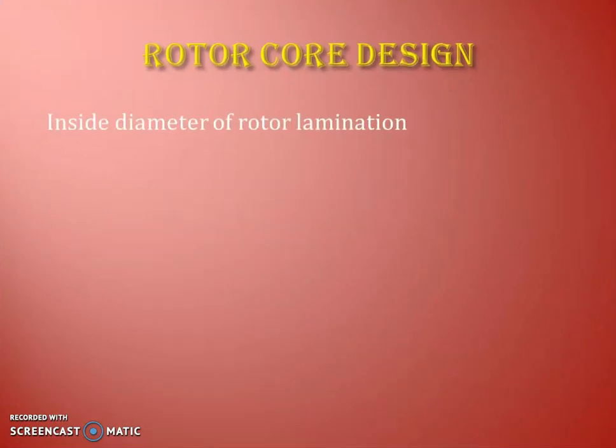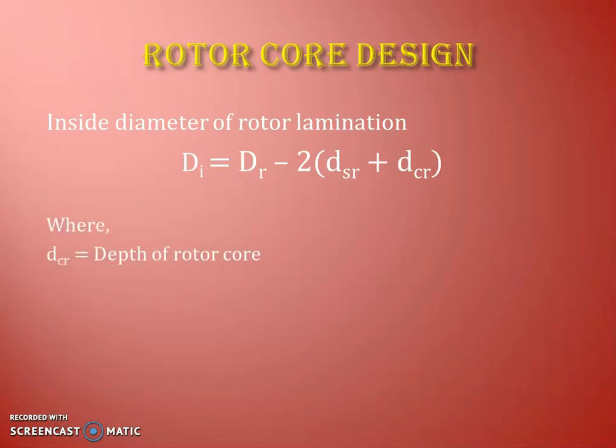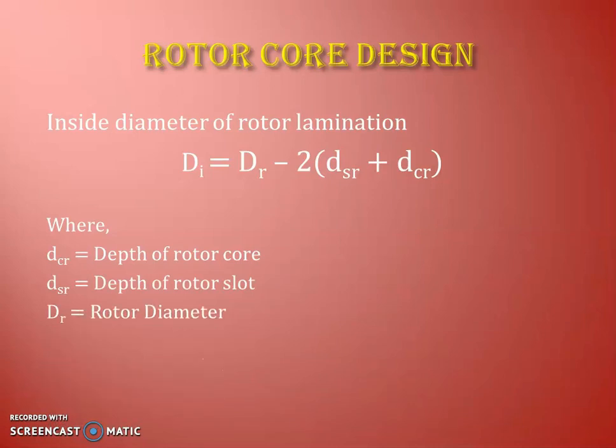To complete the rotor core design, once depth of the rotor core is available, we calculate the inside diameter of the rotor lamination, which is the shaft diameter. Inside diameter di equals rotor diameter dr minus 2 times (dsr — depth of rotor slot) minus 2 times (dcr — depth of rotor core). Based on this equation, we can easily calculate the inside diameter of the rotor lamination. This way we have completed the rotor design for slip ring type motor.